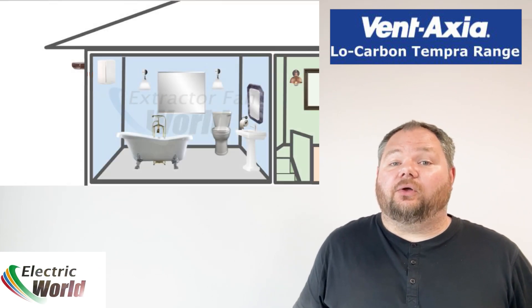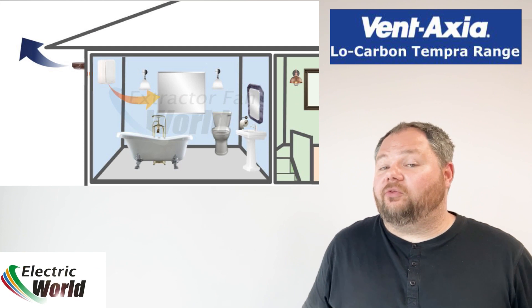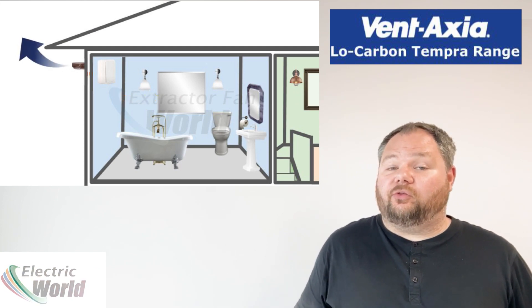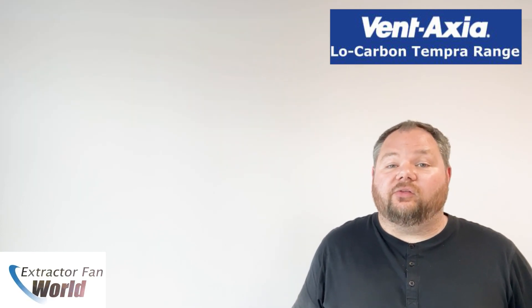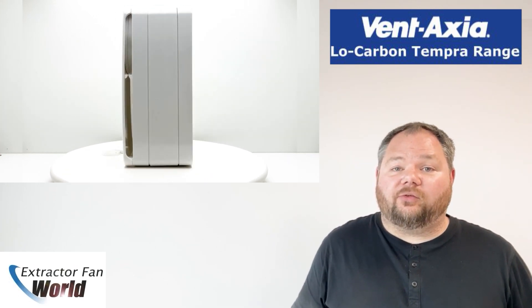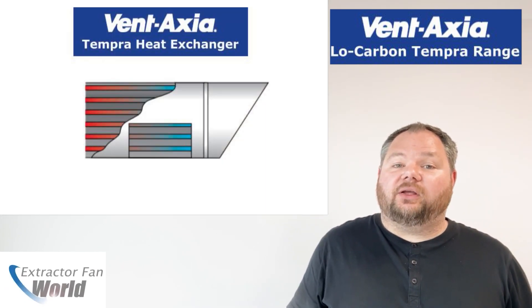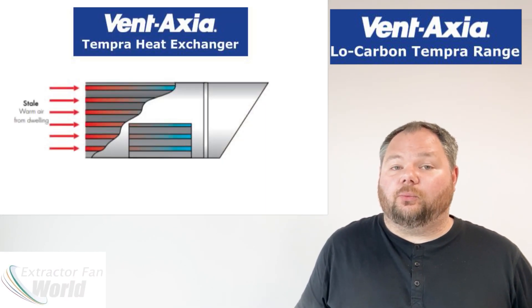The Tempra range combats this by not only extracting air but bringing fresh air back into the property, whilst recovering up to 75% of the heat loss through extraction. Usually used as a continuous running fan with a trigger to boost, the low carbon Tempra will extract steam and moisture like a normal extractor fan, but also draws fresh air back in via a specially constructed heat exchanger mounted through the wall.